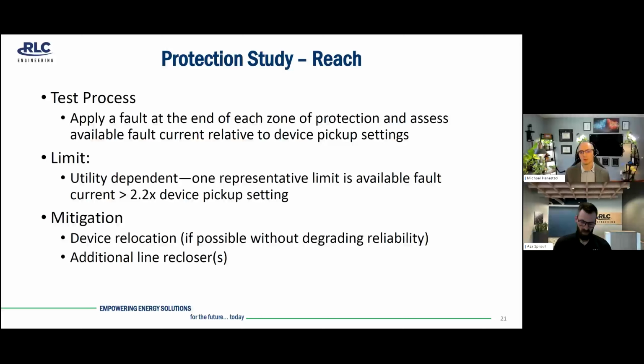A typical, representative criteria that we see is that the available fault current at the end of the zone of protection should be 2.2 times greater than the device pickup. We occasionally also see a high impedance fault being applied at the end, ensuring that the upstream devices can actually detect and trip still. A device relocation could be an option, shifting one of your devices closer to the end of that zone of protection, or additional devices may be required.